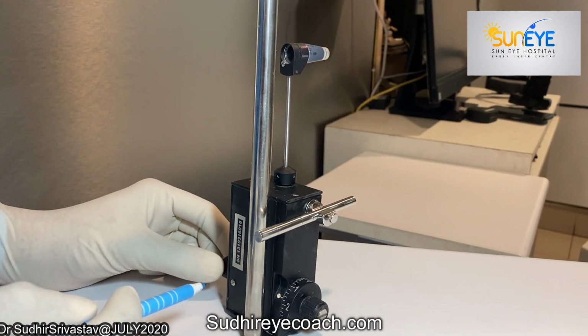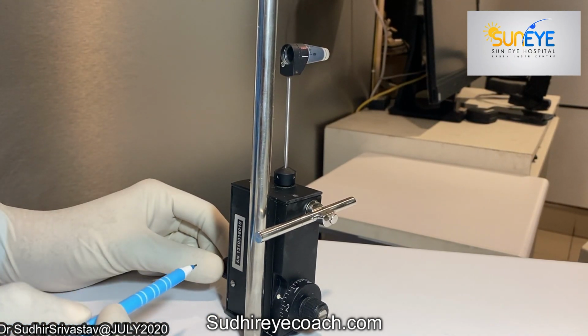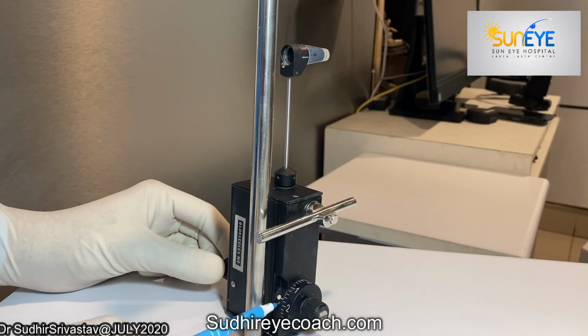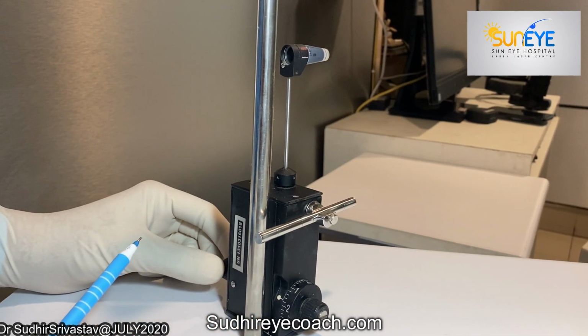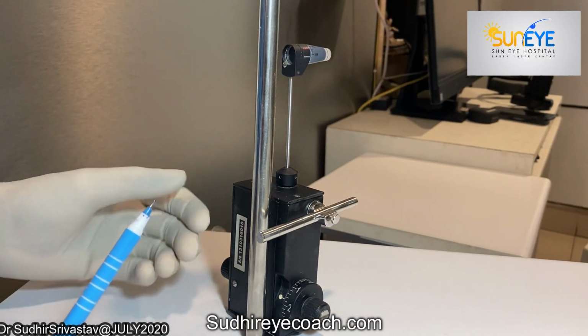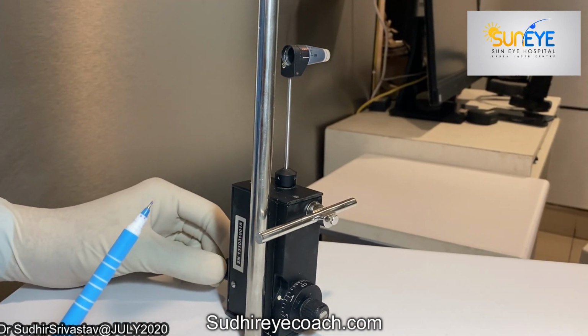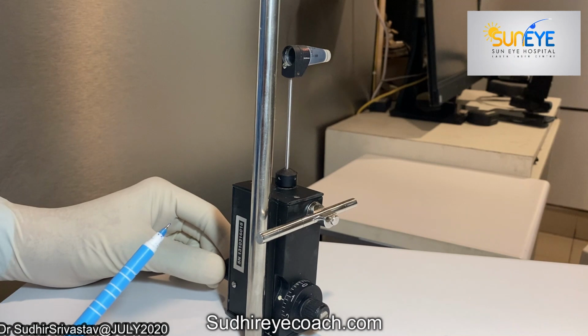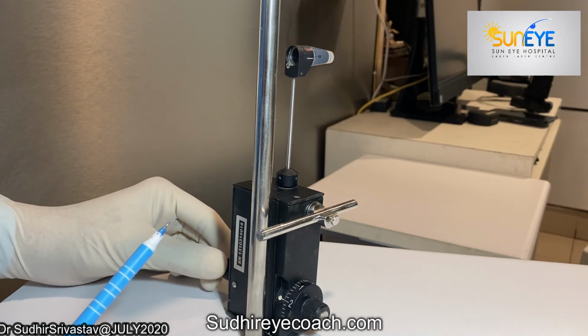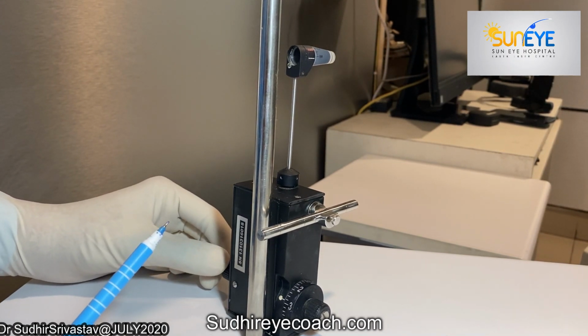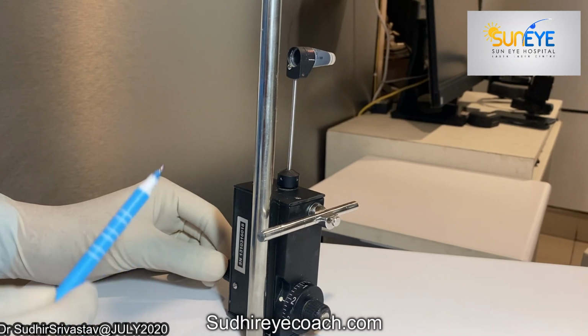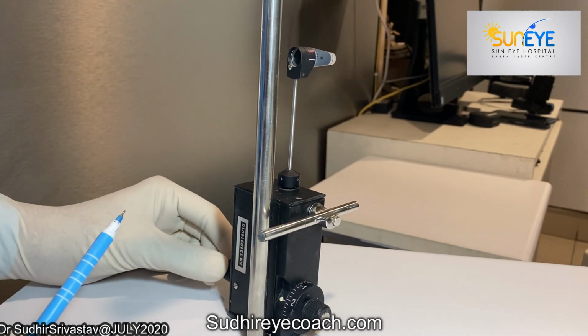Now if the movement of the applanating cone is within the range of 18 to 22 millimeters of mercury, then the tonometer is said to be in good calibration, and we can do it 2 or 3 times by moving the knob from the position 1 to 2 and from 3 to 2 while checking the movement of the applanating cone.